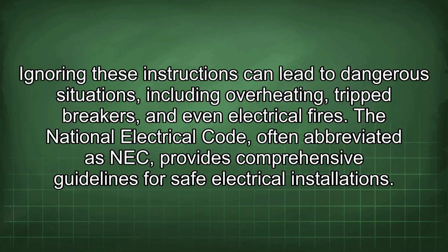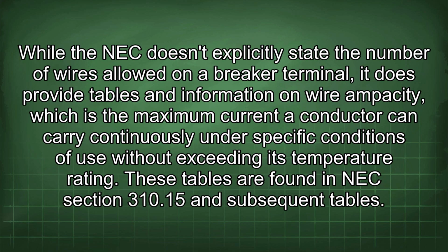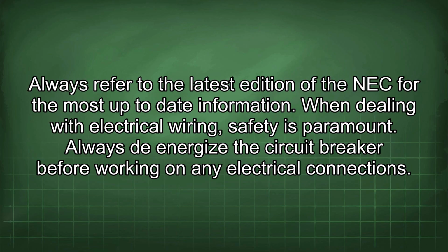The National Electrical Code, often abbreviated as NEC, provides comprehensive guidelines for safe electrical installations. While the NEC doesn't explicitly state the number of wires allowed on the breaker terminal, it does provide tables and information on wire ampacity, which is the maximum current a conductor can carry continuously under specific conditions of use without exceeding its temperature rating. These tables are found in NEC section 310.15 and subsequent tables. Always refer to the latest edition of the NEC for the most up-to-date information.